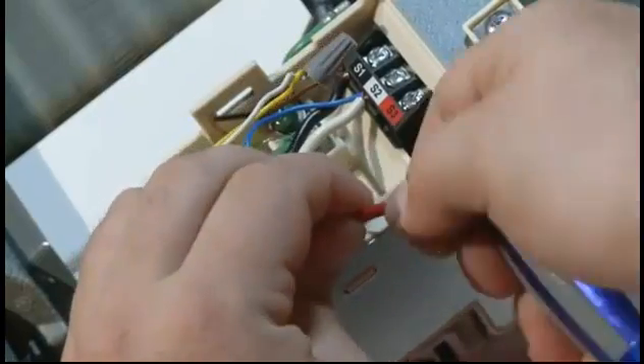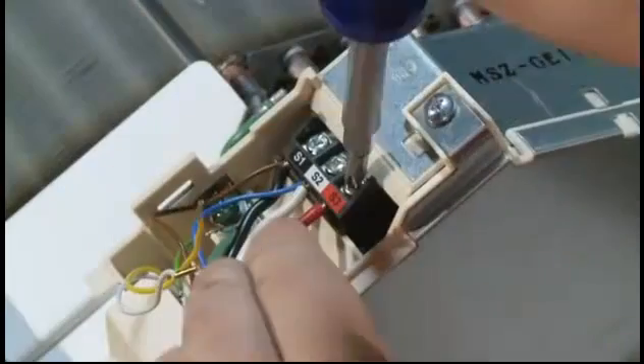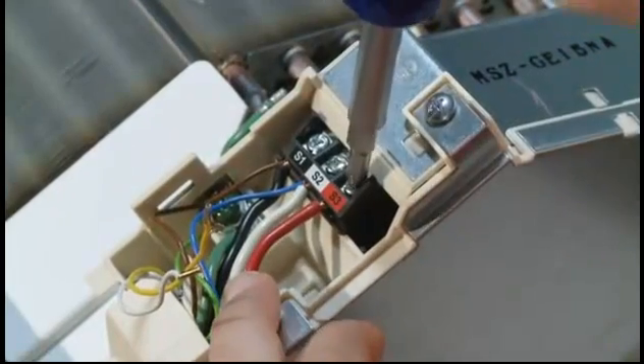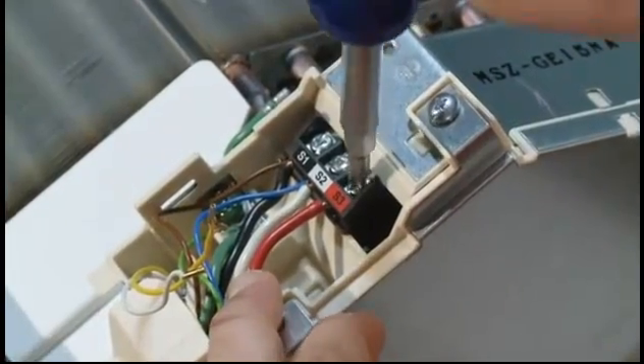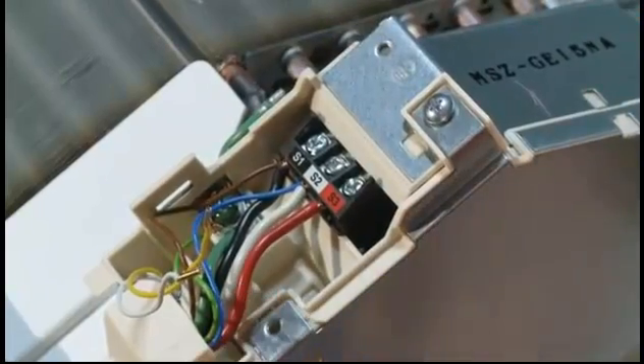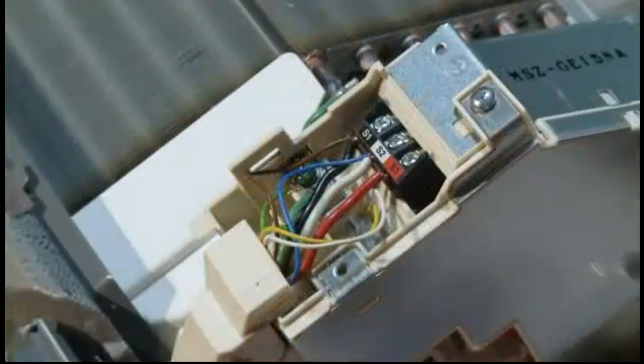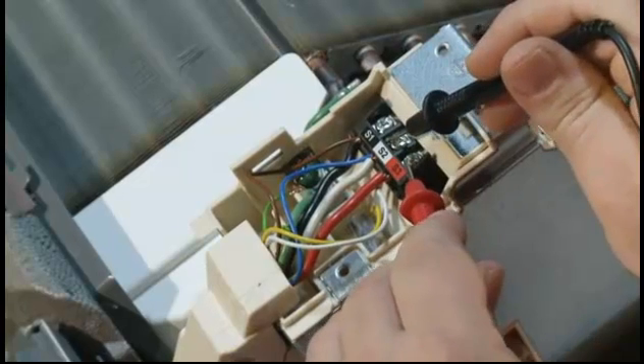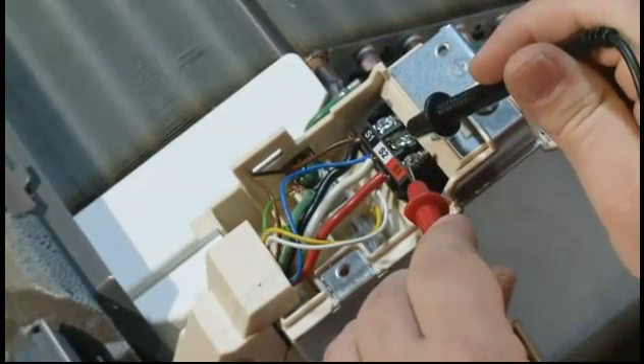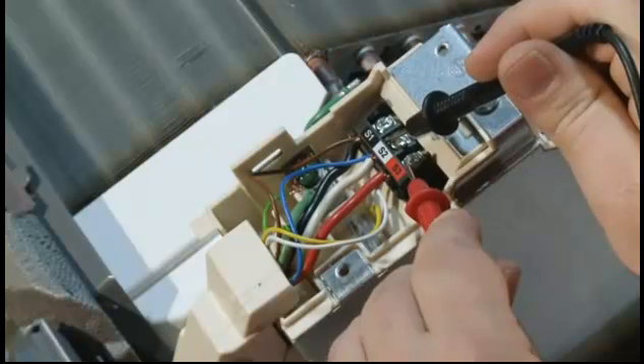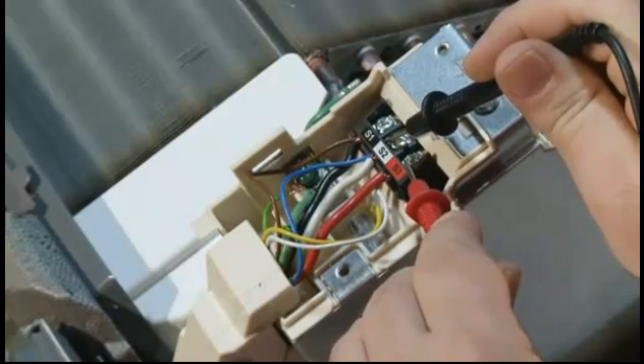We can test this by disconnecting our normally closed and common wires from the S3 and wiring S3 directly to the indoor S3 terminal. Be sure to turn off your outdoor power while doing this for no less than 3 minutes. Once we power back up, we can recheck our DC voltage and should find that we do have a communicating voltage. Now you can determine why the condensate pump safety was activated.